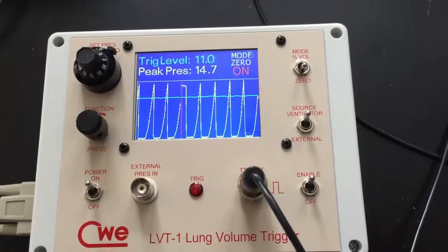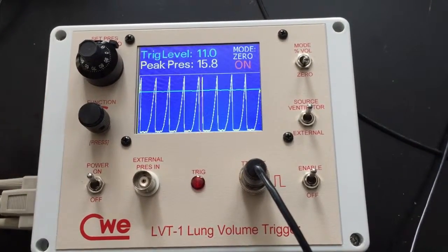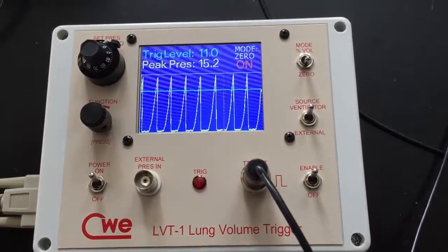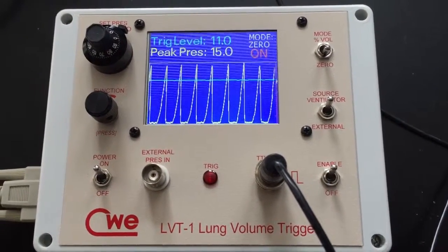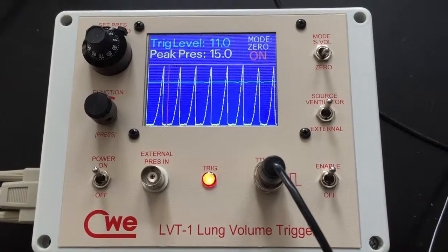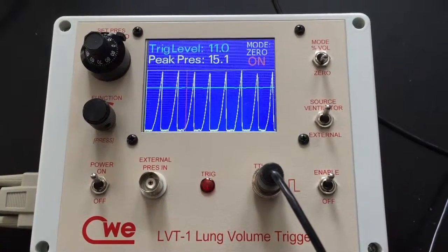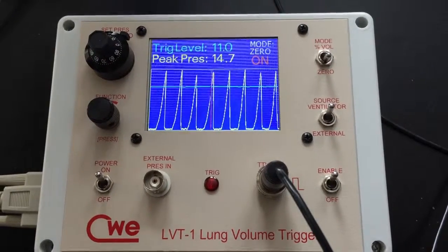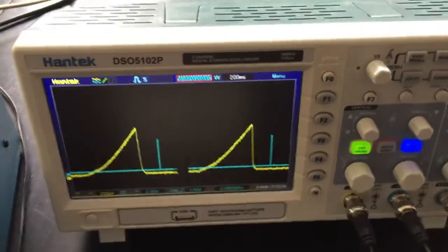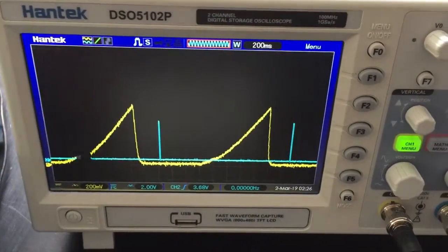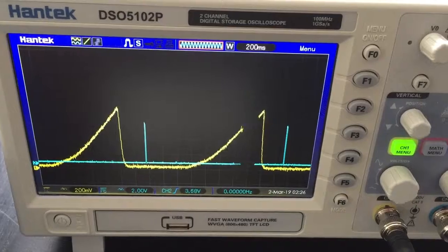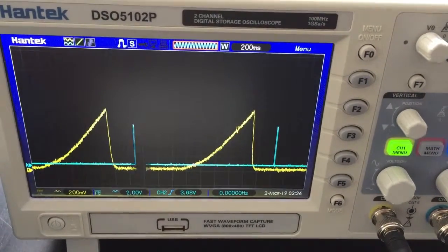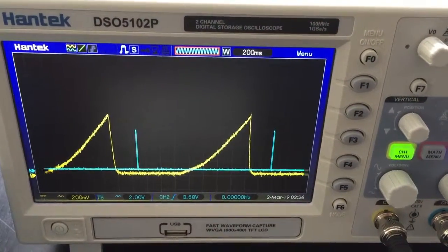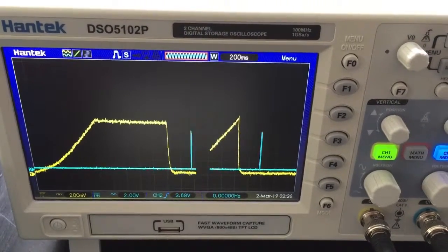volume. So what's happening is the sensors in here are waiting for the pressure to drop close to zero, and then waiting for a preset time to make sure that it's staying at zero, and then it outputs the pulse. And you can see on the oscilloscope that pulse is occurring during the zero phase, where it would be at FRC, or functional residual capacity of the lungs.